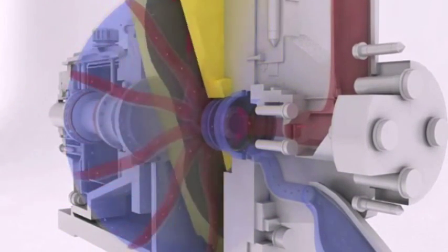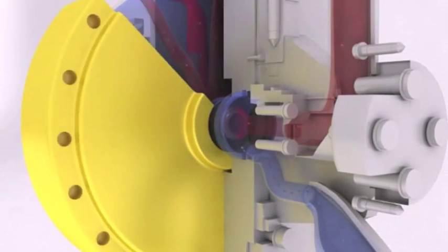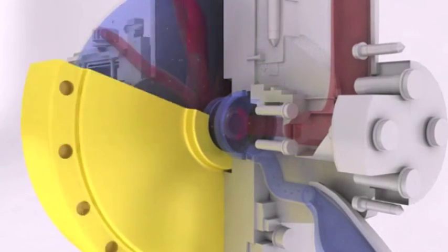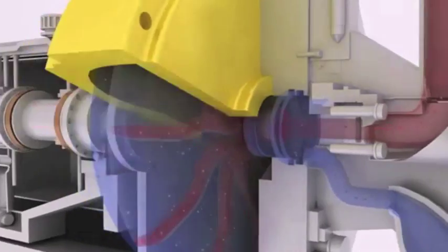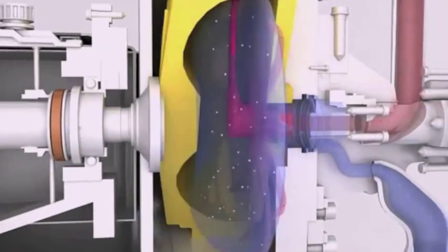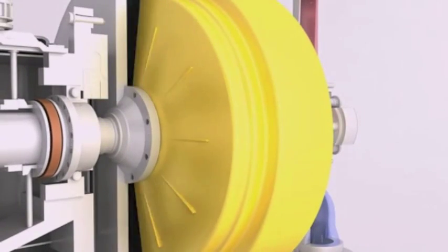The fluid enters the pump at the suction inlet and passes through the low-pressure mechanical seal. The fluid then enters the rotor, which is rotating within the pump casing. The fluid is accelerated through the rotor channels, which at this point generate approximately half of the overall outlet pressure.